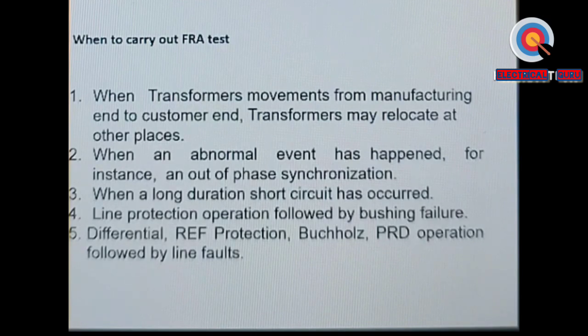On arrival at site, before we unload the transformer from the trailer, this test is performed again to ensure that no movement of parts has taken place inside during transport. Once we are assured that the transformer geometry is intact on arrival, only then do we unload the transformer. So the test is performed before shipment from the manufacturer's works and on arrival at the customer's end.